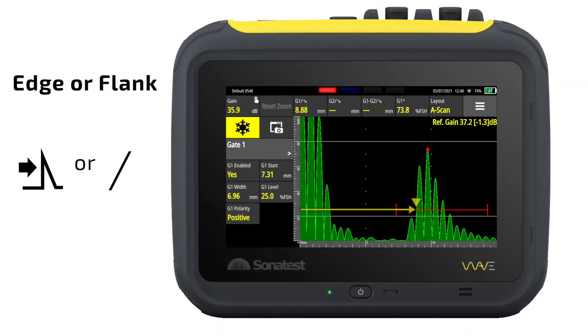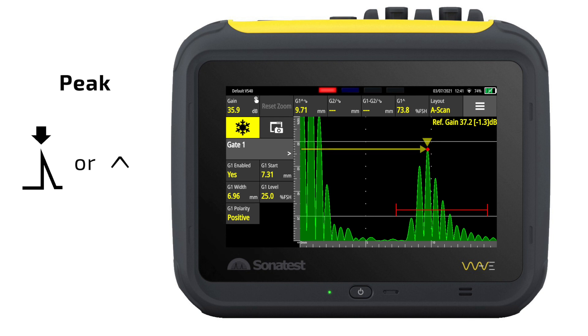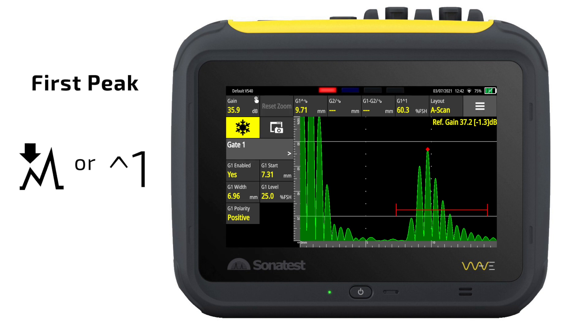For the purposes of distance, edge, flank, and J-flank are all the same thing. They take the distance at the point at which the leading edge of the waveform crosses the gate. Peak looks at the whole waveform within the gate and takes the distance reading to the point of maximum amplitude. First peak mode is fairly self-descriptive — if there are more than one peak that crosses the gate, it will simply look at the peak position of the first lobe.